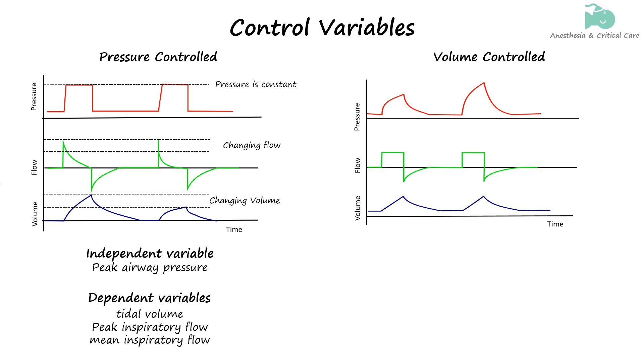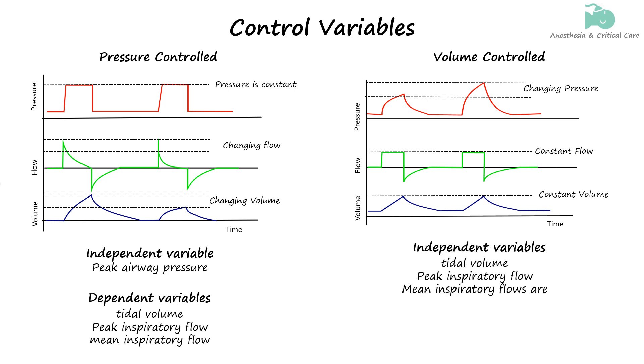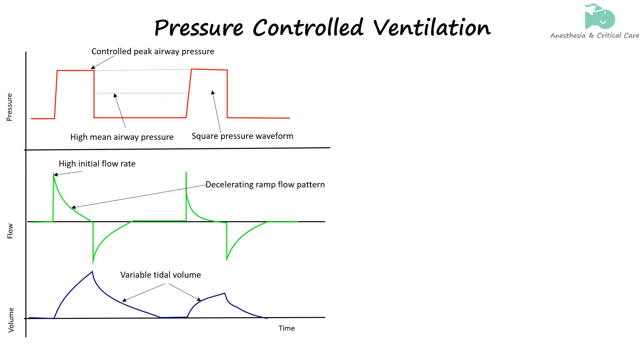When volume is controlled in a ventilation mode, the waveforms of the volume-time and inspiratory-flow-time curves remain unchanged in response to variations in the respiratory impedance of the system. In contrast, the pressure-time curve undergoes changes in both waveform and values. So inspiratory flow and tidal volume become the independent variables, and airway pressure becomes the dependent variable. Now let us further extend our understanding of pressure control to understand how it compares to volume control clinically.